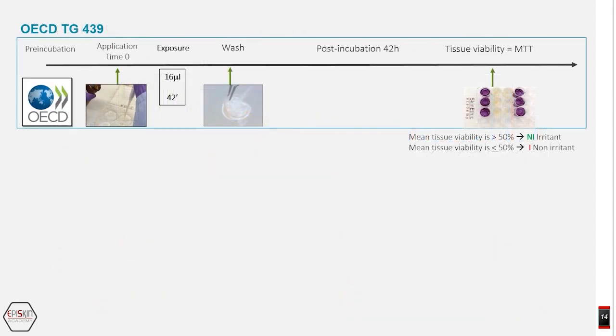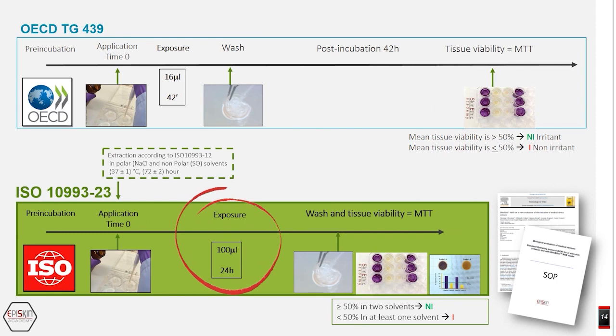If we compare the final protocol for medical devices to the OECD protocol, what we can observe is that the main differences concern the volume: 16 microliters for OECD, 100 microliters for medical devices. The time of exposure: 42 minutes for chemicals, 24 hours for medical devices, and no post-incubation. At the end, the readout is the same, cell viability, and your medical device is considered non-irritant if your mean cell viability is superior to 50% in the two solvents.